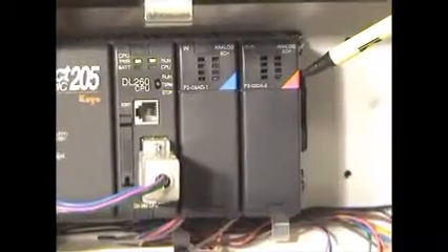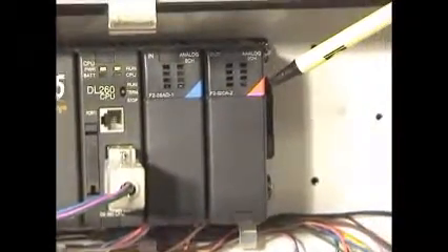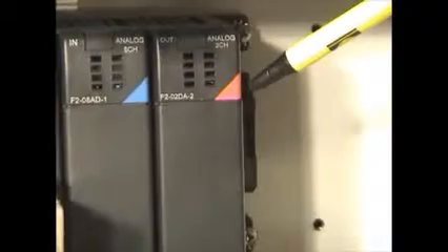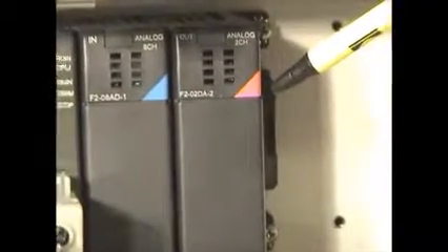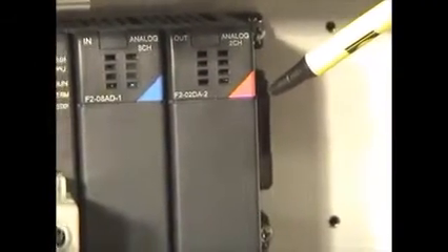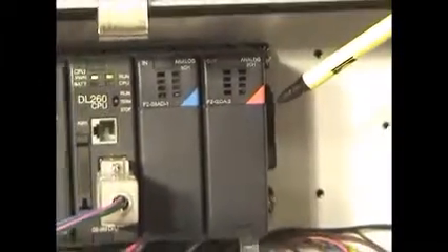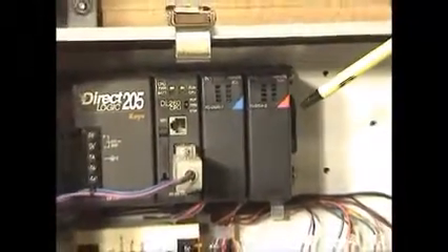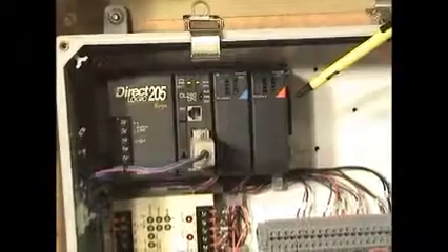The next module is the analog out module. This unit sends a 0 to 5 volt DC to the open coil of the proportional valve to allow the hydraulic cylinder to open the butterfly valve. This voltage is displayed on the front panel of the enclosure.